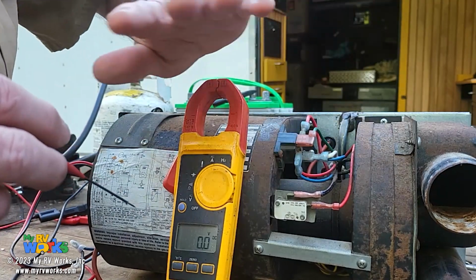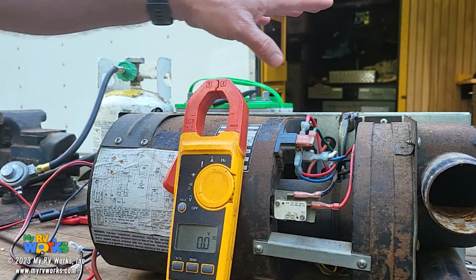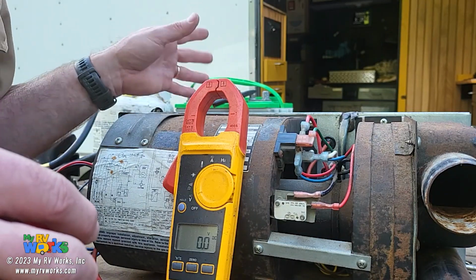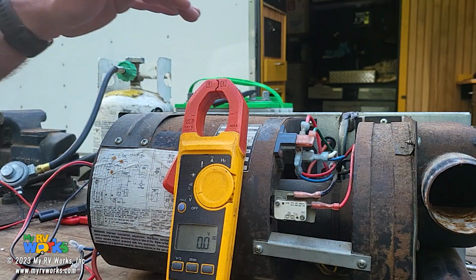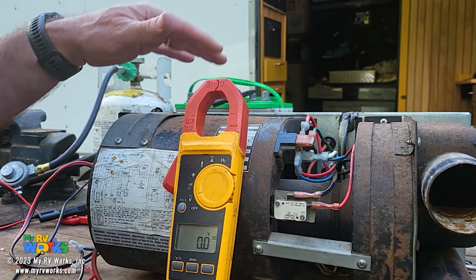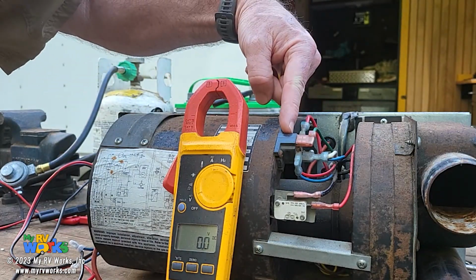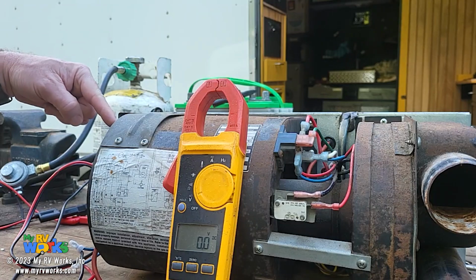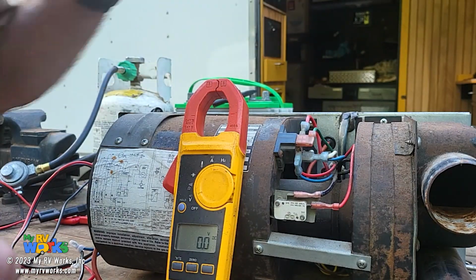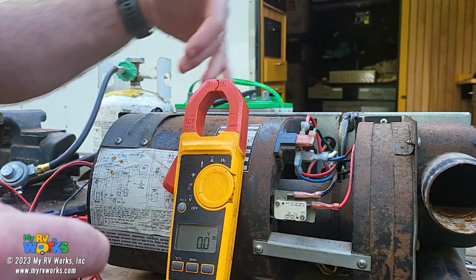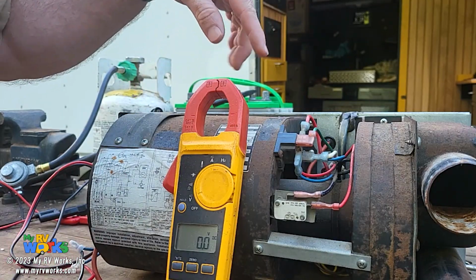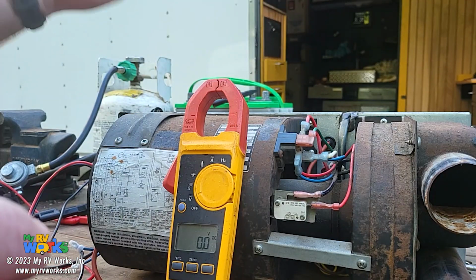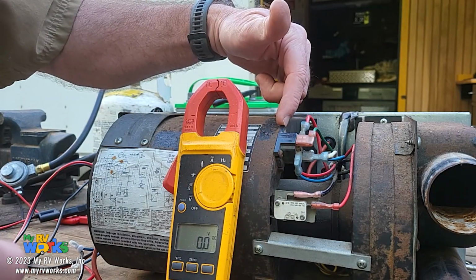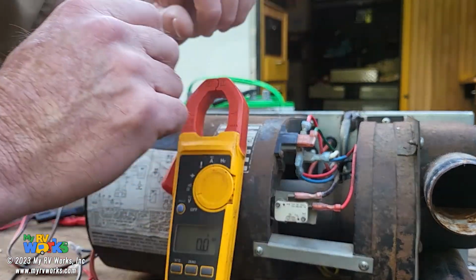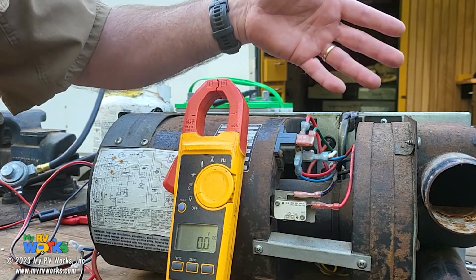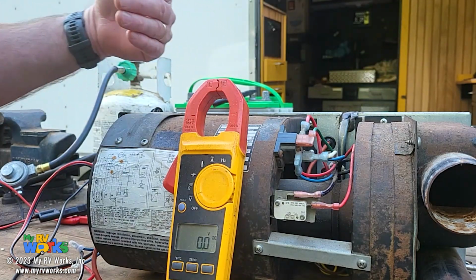Okay, so this furnace will run forever until somebody goes inside and turns the thermostat off. They do have control boards that will fix this problem, but as long as this relay is separate from the control board, it does not understand that there's no flame. There's no connection between this relay and that control board to say, my flame is extinguished, therefore turn off. Okay, so that's why your furnaces will run forever, blowing cold after it's tried 3 times.